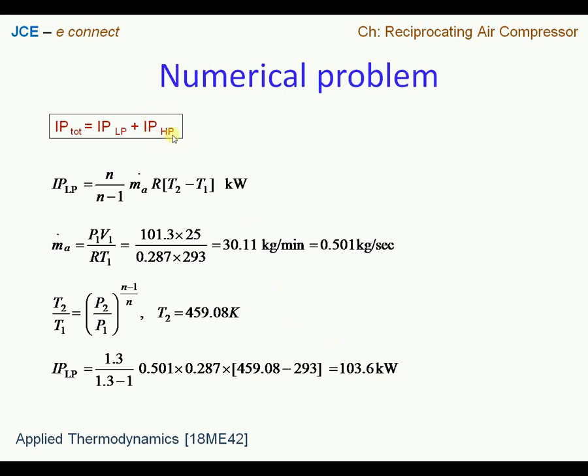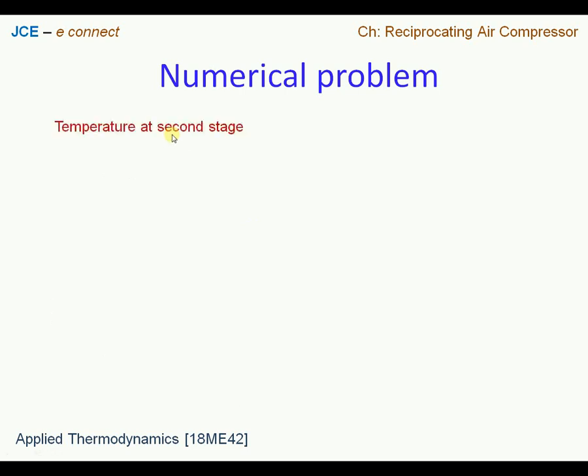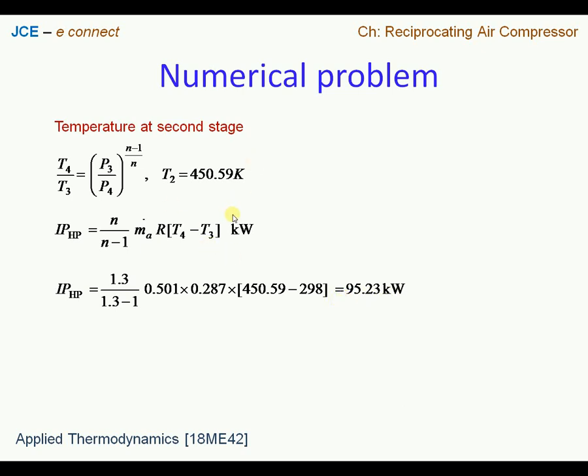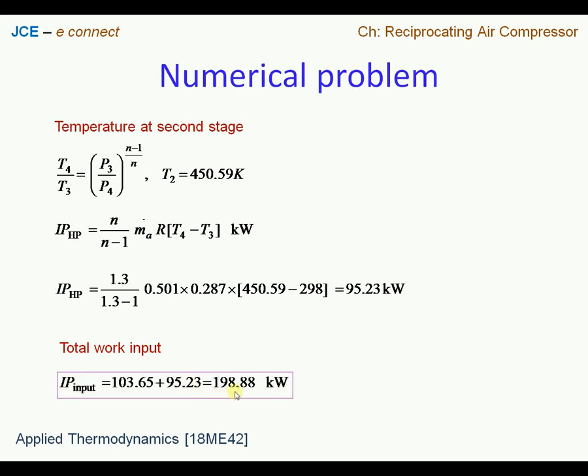Plugging all terms into the equation gives the indicated power for the low pressure cylinder as 103.6 kW. For the high pressure cylinder, the same steps are followed: temperature T4 is found using the isentropic relation, and these values are substituted into the standard indicated power equation, giving IP for the high pressure cylinder as 95.23 kW. The total work input is the sum of both, giving the total power for the two-stage compressor.